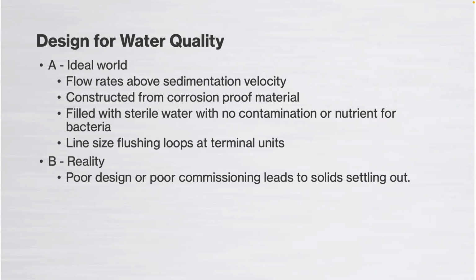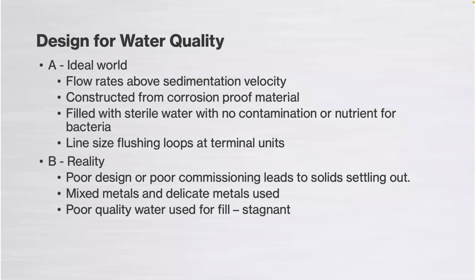And that's really important. The commissioning phase is absolutely vital, and the commissioning engineers, or commissioning technicians, should pick up if there's anything that needs to be changed. They should be coming on site with the water treatment company, the commissioning team, even before the water treatment company make a start.